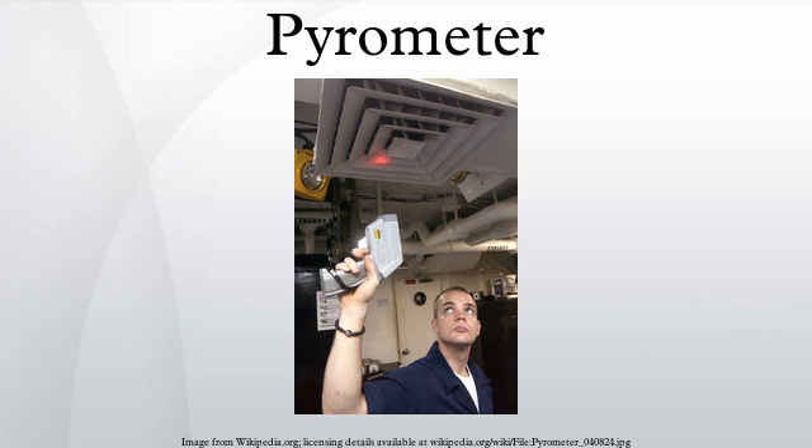In the smelter industry, temperature is a fundamental parameter in metallurgical furnace operations. Reliable and continuous measurement of the melt temperature is essential for effective control of the operation. Smelting rates can be maximized, slag can be produced at the optimum temperature, fuel consumption is minimized, and refractory life may also be lengthened. Thermocouples were the traditional devices used for this purpose, but they are unsuitable for continuous measurement because they melt and degrade.